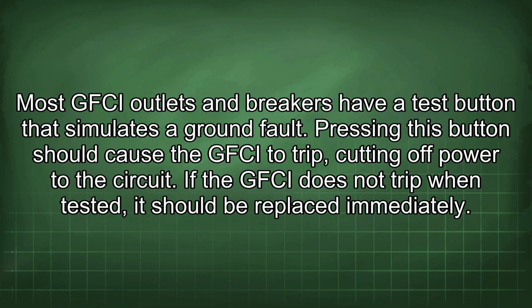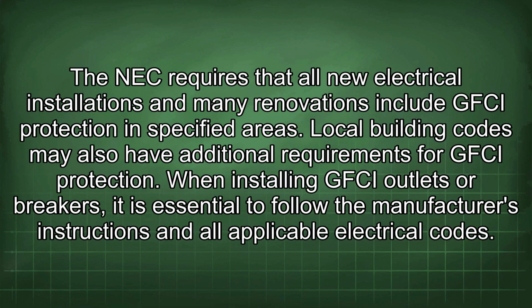If the GFCI does not trip when tested, it should be replaced immediately. The NEC requires that all new electrical installations and many renovations include GFCI protection in specified areas. Local building codes may also have additional requirements for GFCI protection. When installing GFCI outlets or breakers, it is essential to follow the manufacturer's instructions and all applicable electrical codes.